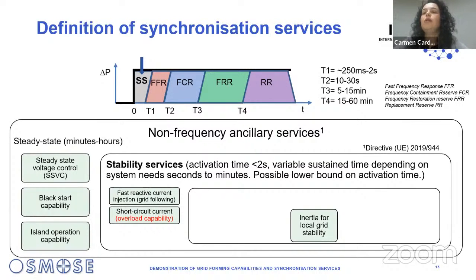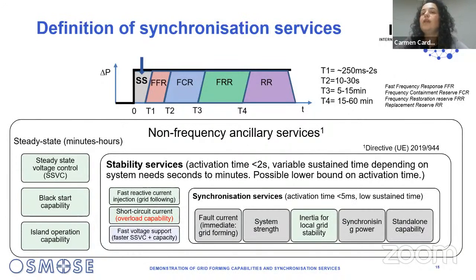And we have been speaking for a while now about inertia for local grid stability. And actually, this is where we need to fit these synchronization services, because there is not only this local inertia concept that is needed to maintain stability on a local scale in a system dominated by power electronics. What we'd like to highlight here is that there is a difference between these services. We cannot treat them as one only family, because we need to separate the requirements that apply in steady state, the ones that are quite fast but still leave room for measurements, like the stability services, from the synchronization services, which need to be activated immediately and have quite low sustained time.